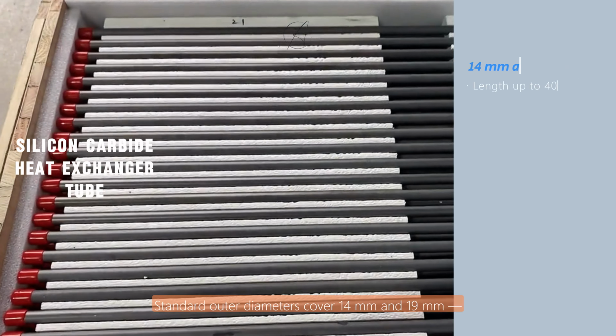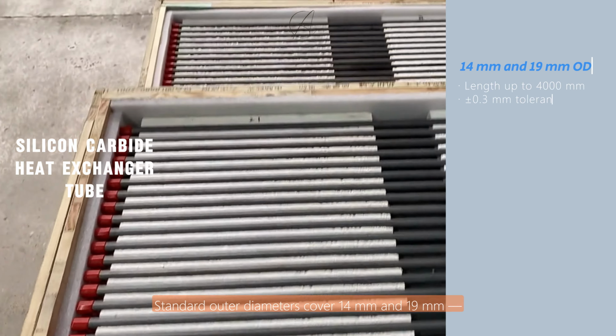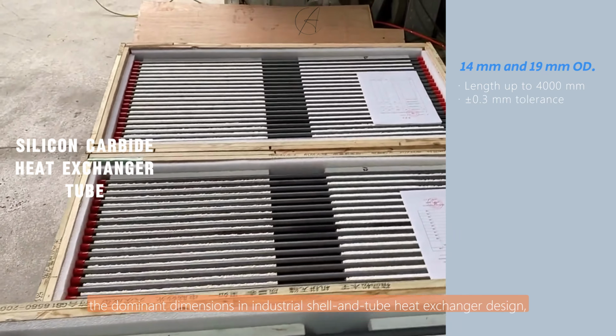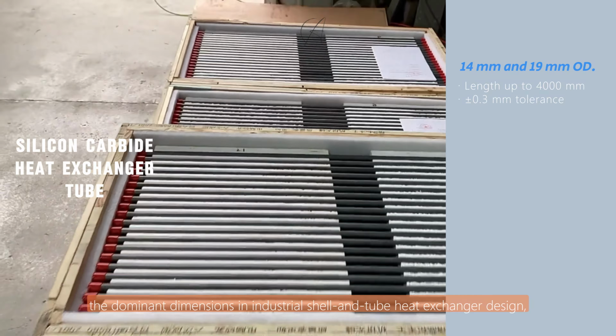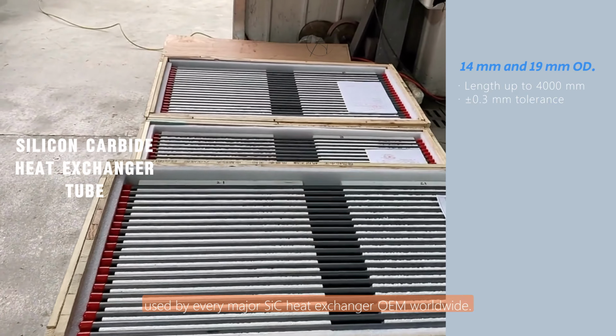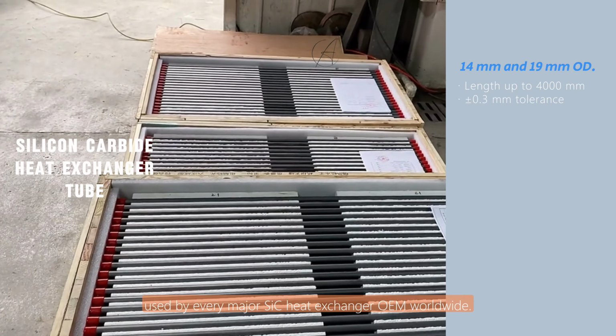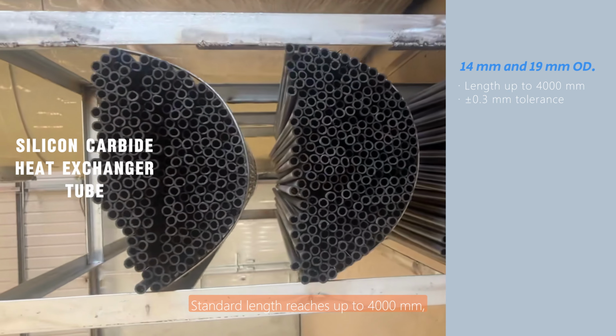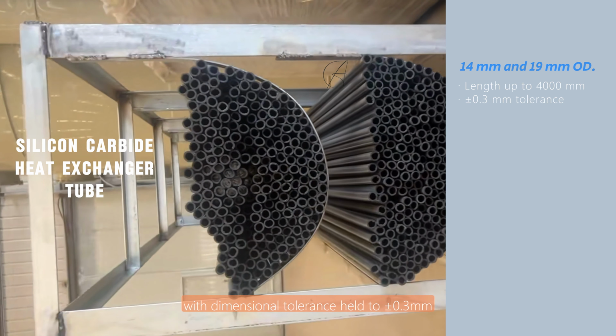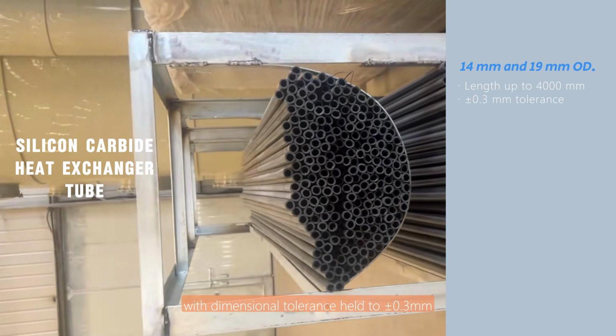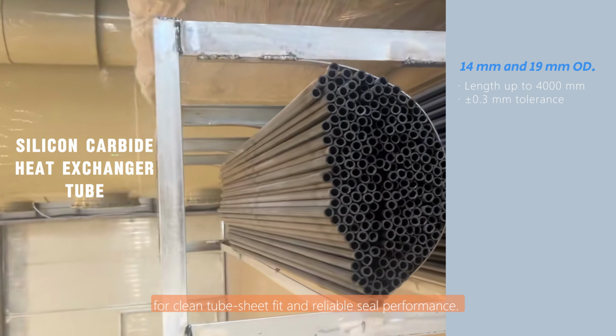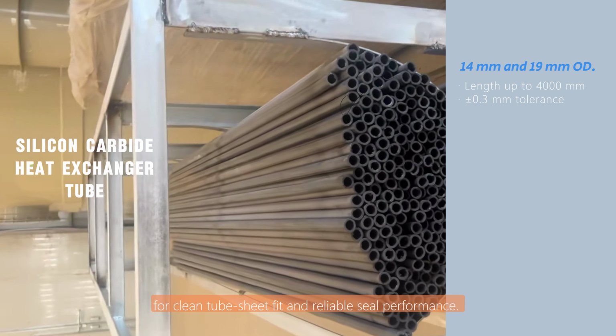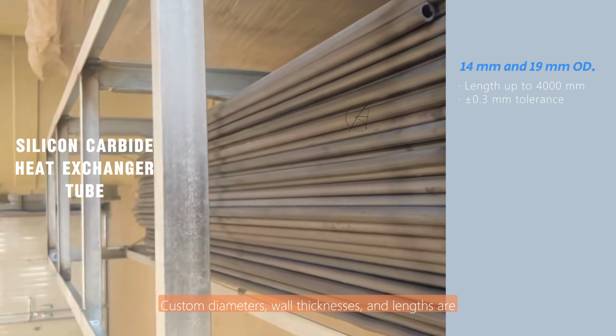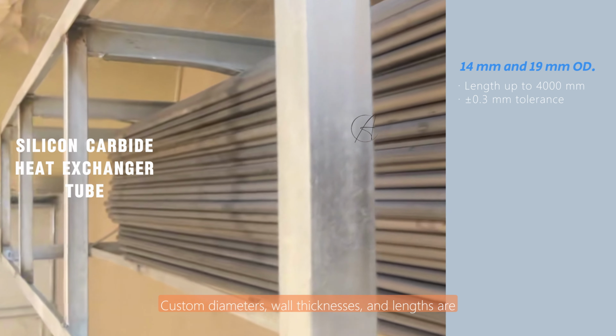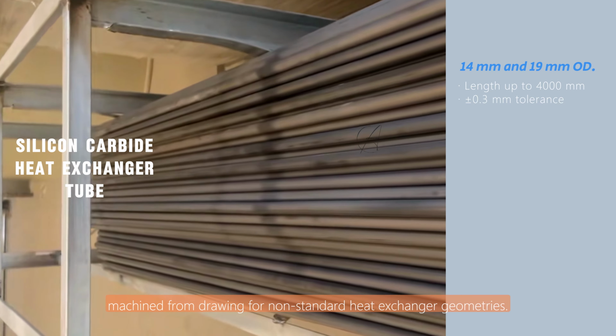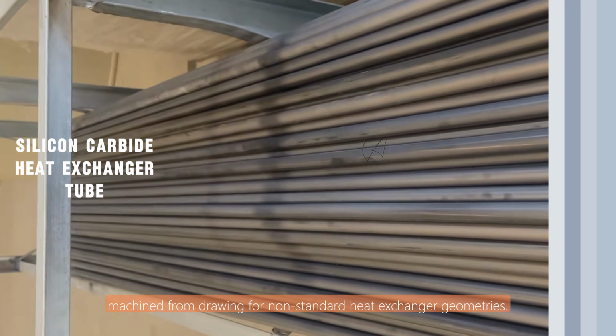Standard outer diameters cover 14 mm and 19 mm, the dominant dimensions in industrial shell and tube heat exchanger design, used by every major SiC heat exchanger OEM worldwide. Standard length reaches up to 4,000 mm, with dimensional tolerance held to plus or minus 0.3 mm for clean tube sheet fit and reliable seal performance. Custom diameters, wall thicknesses, and lengths are machined from drawing for non-standard heat exchanger geometries.